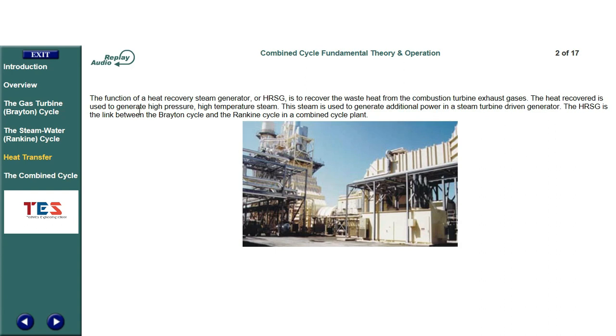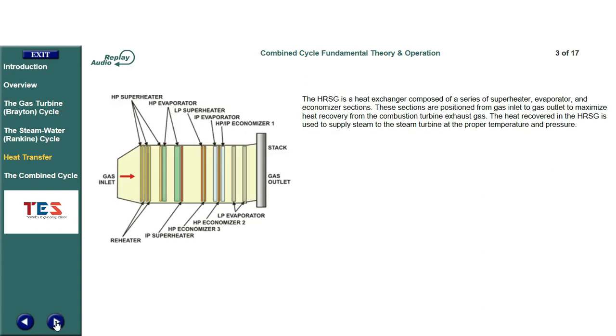The heat recovered is used to generate high pressure, high temperature steam, which is used to generate additional power in a steam turbine-driven generator. The HRSG is the link between the Brayton cycle and the Rankine cycle. The HRSG is a heat exchanger composed of a series of superheater, evaporator, and economizer sections, positioned from gas inlet to gas outlet to maximize heat recovery from the combustion turbine exhaust gas. The heat recovered in the HRSG is used to supply steam to the steam turbine at the proper temperature and pressure.